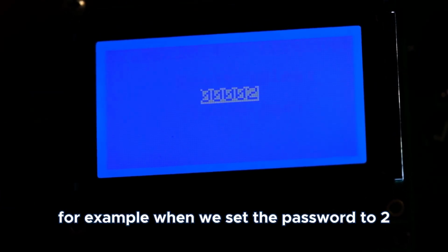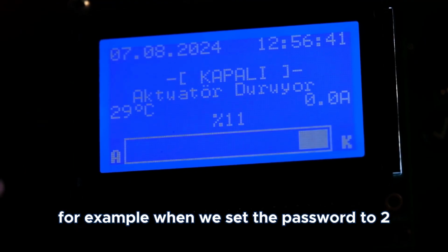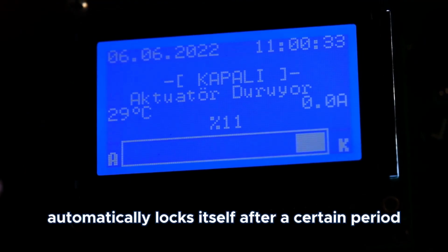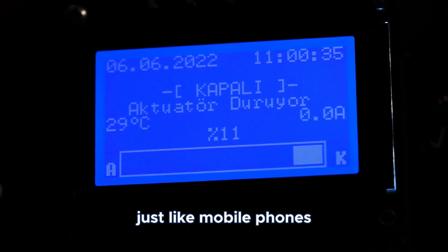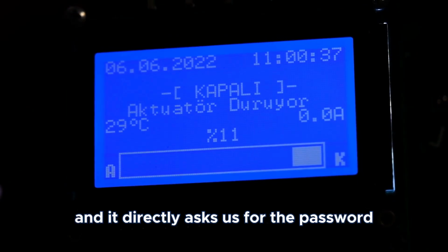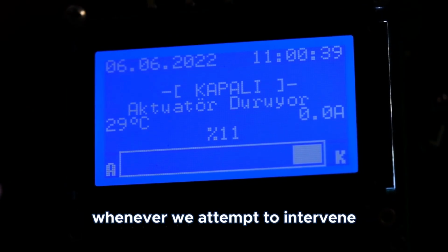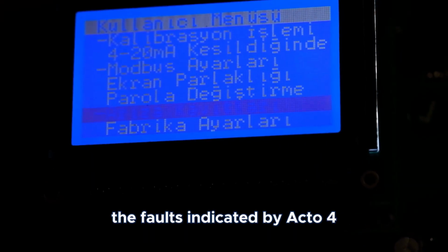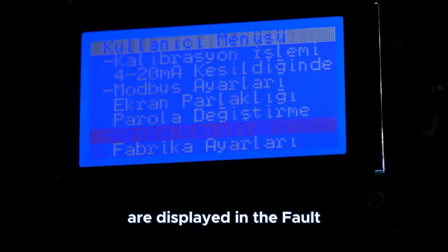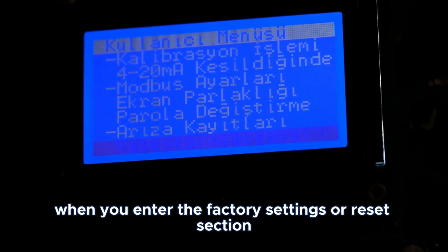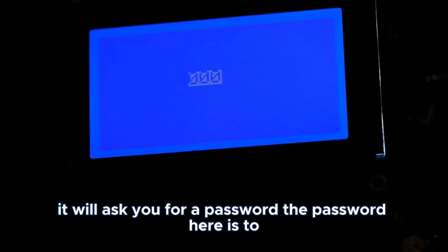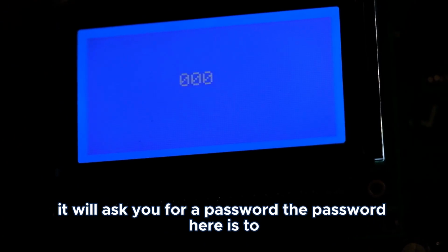For example, when we set the password to 2, the actuator automatically locks itself after a certain period, just like mobile phones, and it directly asks us for the password whenever we attempt to intervene. The faults indicated by the actuator are displayed in the fault log menu. When you enter the factory settings or reset section, it will ask you for a password. The password here is 2.